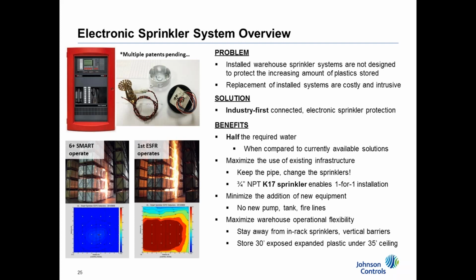So the electronic sprinkler system can use water a lot more efficiently. You use really half the amount of water as compared to the closest alternative in case of, say, an exposed expanded plastic scenario at 35 feet, and you're able to provide the same level of fire protection with the electronic sprinkler. There's really no need to change the pipes. So you can use the 3/4 inch thread size ESFR K17. That's a sprinkler that most of you are maybe familiar with. And in most cases, it means there are no new pumps or fire tanks, which can be a major cost driver in a retrofit scenario, which is really what we're trying to target at this point with the electronic sprinkler. So what you're able to do is minimize disruption to your existing warehouse and, of course, maximize the operational flexibility.